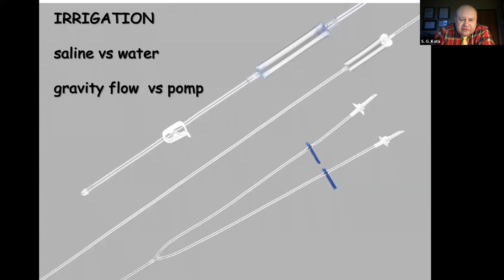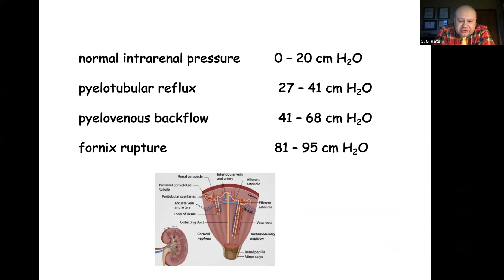It is an experimental study, of course, but the normal intrarenal pressure of fluid or urine inside is between 0 and 20 centimeters of water column. We can observe reflux into tubules when pressure reaches 27 to 41 centimeters of water column. Backflow into veins happens when pressure reaches between 40 and 68 or 70 centimeters of water column, and we can rupture the calyx or fornix of the calyx when pressure reaches 81 to 95 centimeters of water column.